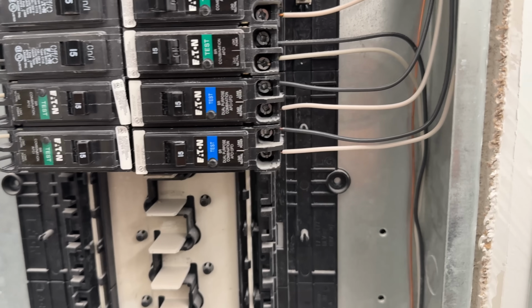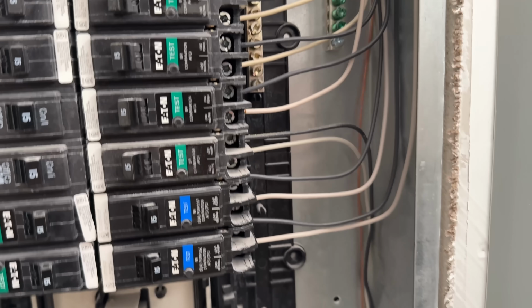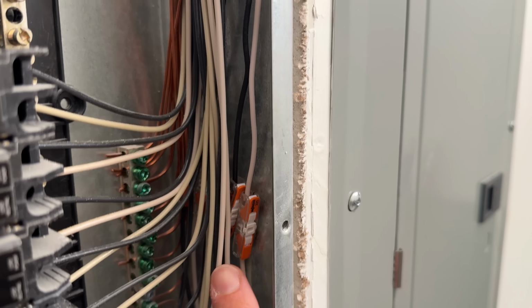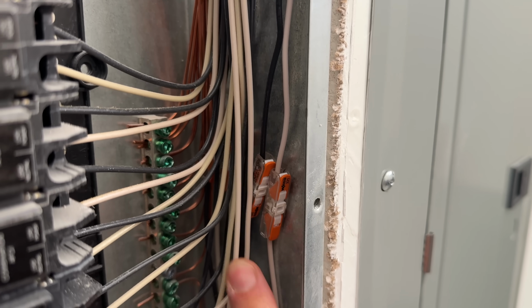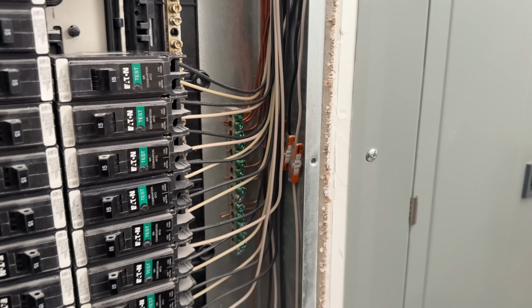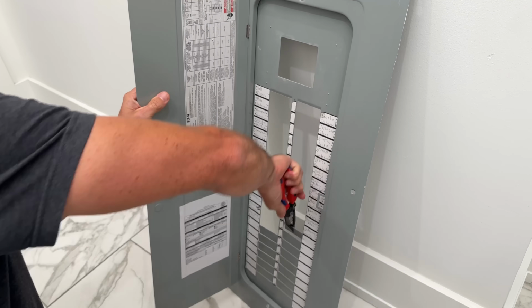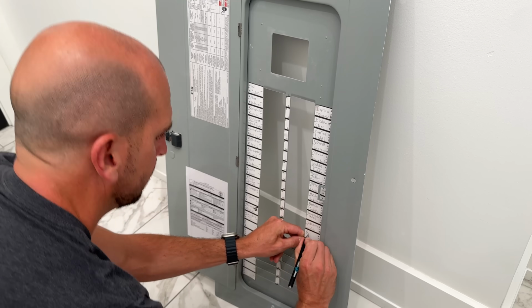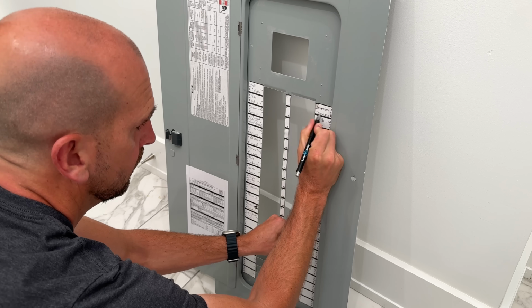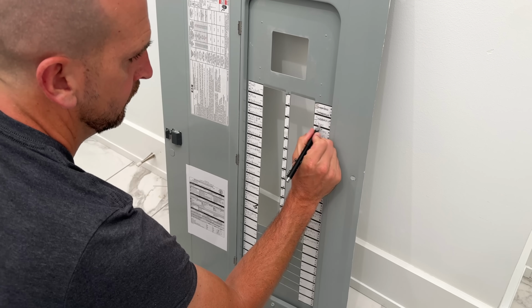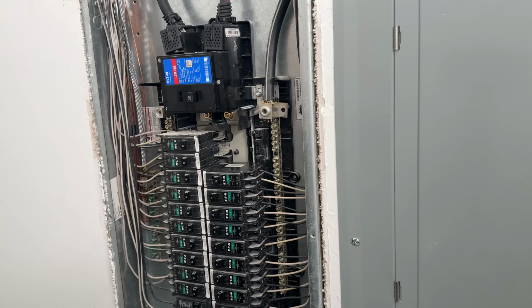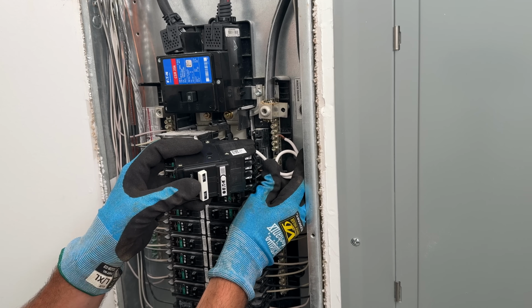Then I just repeated the process for the second one there with both of them in place. Now you can see why I like the inline splices so much, especially compared to the old way, which was using wire nuts. And since we made modifications, you'll want to take your cover. You might need to adjust and open up some slots so you don't have any interference, and also adjust your labels to what your as-is work is now, not what it used to be.